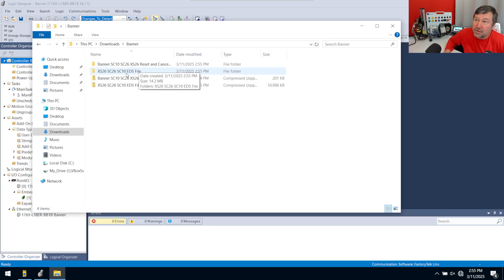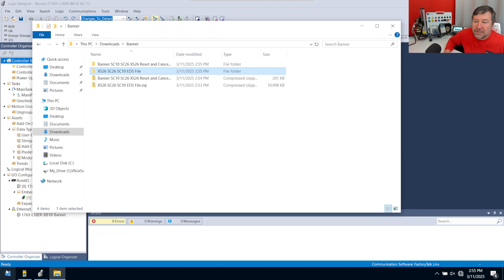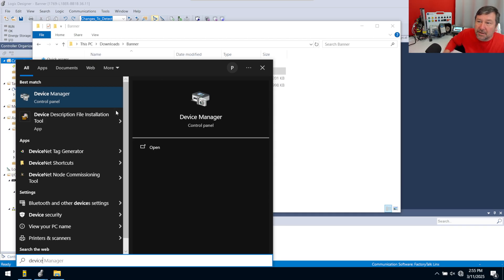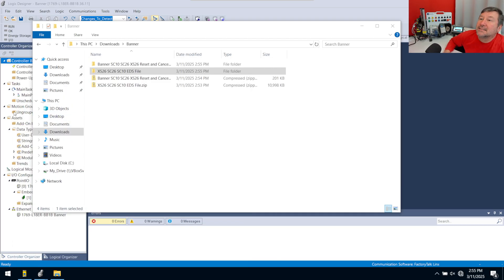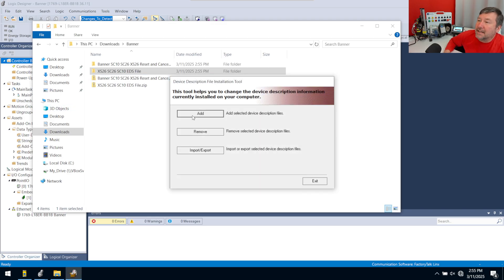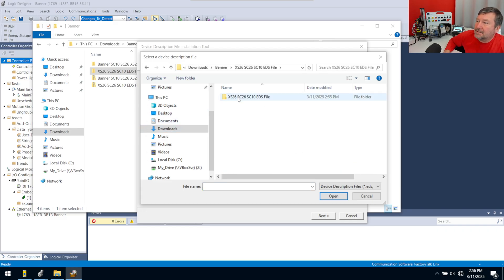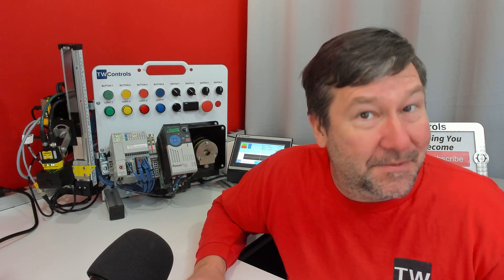Then go ahead and extract both of those files. For the EDS file, go to your Start menu and start typing 'device' and you're going to see the Device Description File Installation Tool. Click it, hit Add, browse to grab that EDS file, and then just hit Next all the way through the prompts and hit Finish — and magically that will get it into Studio 5000.